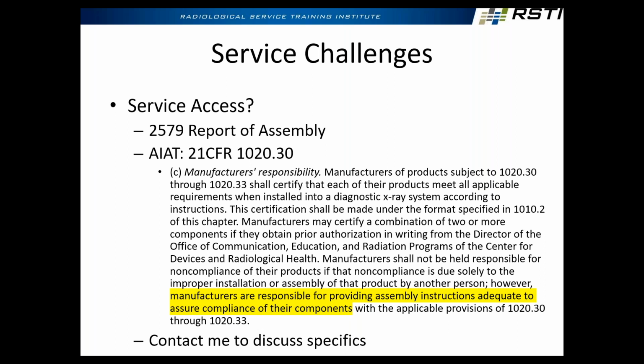but if it makes X-rays or is in the beam, it's a certified component. Why do you think the FDA wants a form filled out anytime a certified component is replaced? Any guesses? They want to make sure you did what? Yeah, it's patient safety. They want to make sure you put this X-ray tube in and calibrated it properly, so the dose is what the screen says it is. They want to make sure that the collimator is working properly, that the inverter is working properly. It's all about patient safety. So you guys don't work for the OEM, but you still had to fill out the 2579 form. The OEM does as well.